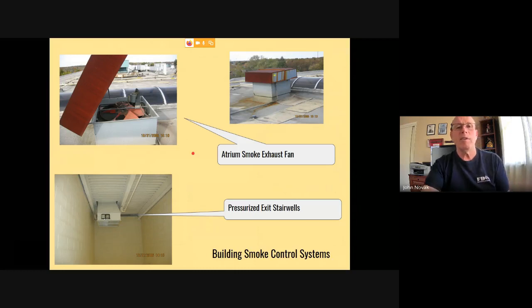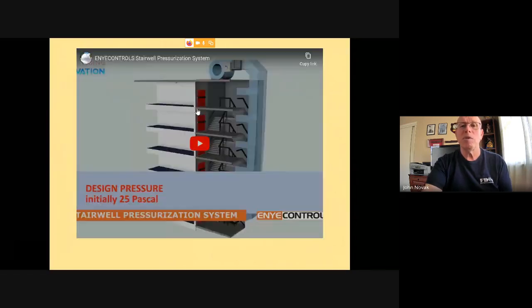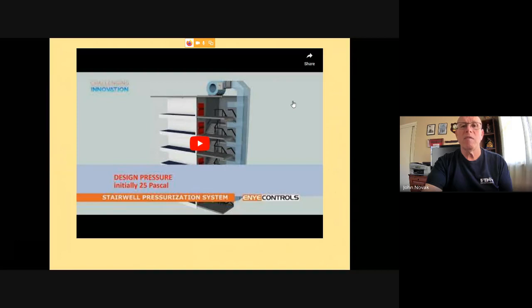But again, you need to go out there and you need to know your buildings. I know that first picture I showed you with that residential building that I have, that was designed so that when the fire alarm went off in one of the wings, that floor's smoke control system would go into exhaust, and the surrounding floors above and below, every level, would go into pressurization. So basically, keeping the smoke compartmentalized to that one wing. So again, you need to know your buildings. So here is a real quick video on stairwell pressurization.